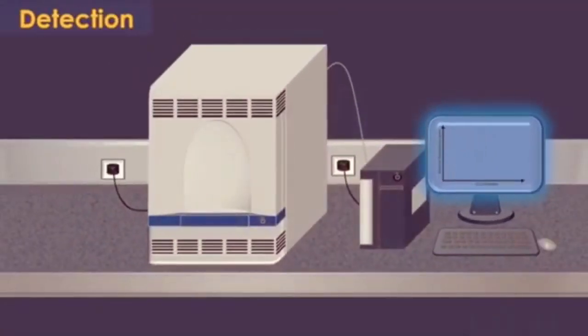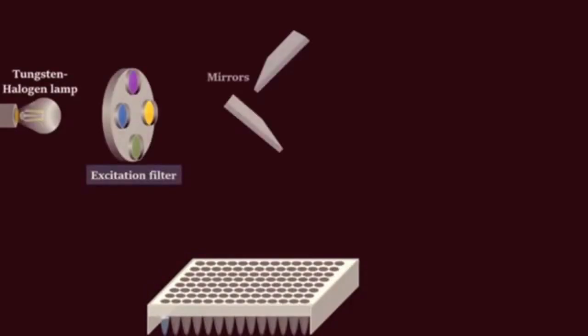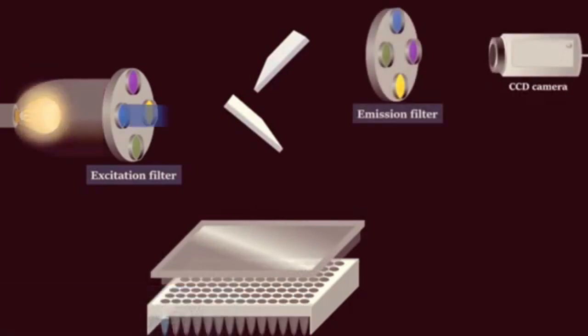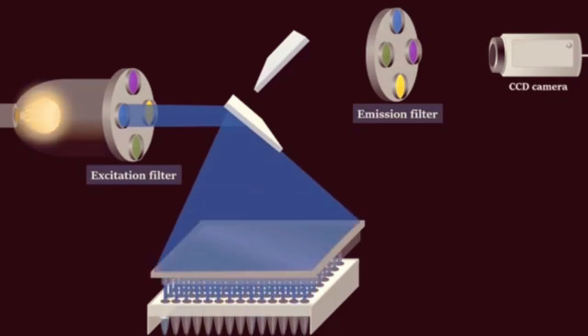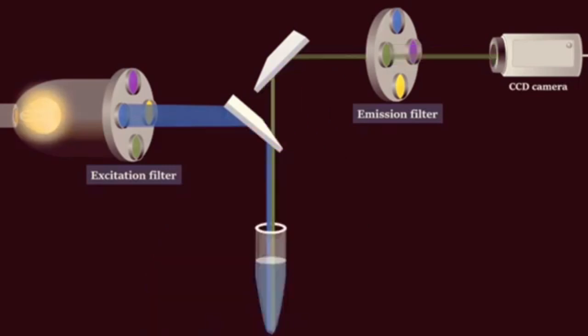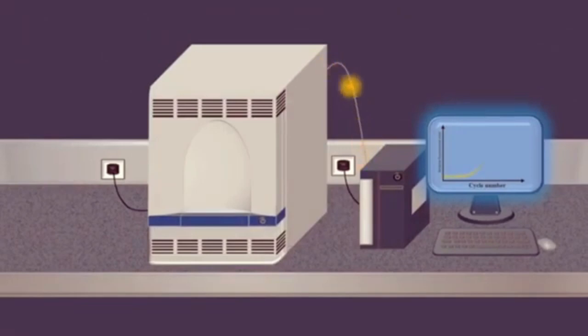For the measurement of the fluorescent signal, a tungsten halogen lamp, an excitation filter, mirrors, lens, an emission filter, and a charge coupled device CCD camera are used. Filtered light from the lamp is reflected off mirror, passes through a condensing lens, and is focused into the center of each well. Then fluorescent light emitted from the wells reflects off the mirror, passes through an emission filter, and is detected by the CCD camera. In each PCR cycle, light from excited fluorophore can be detected by the CCD camera, which converts the light that it captures into digital data. This method is known as real-time PCR, which allows the monitoring of the progress of the PCR reaction as it occurs in real-time.